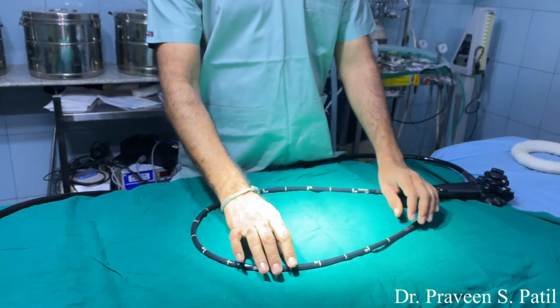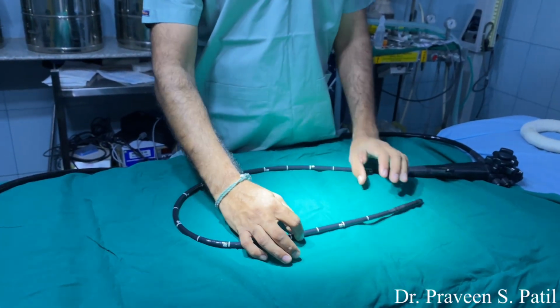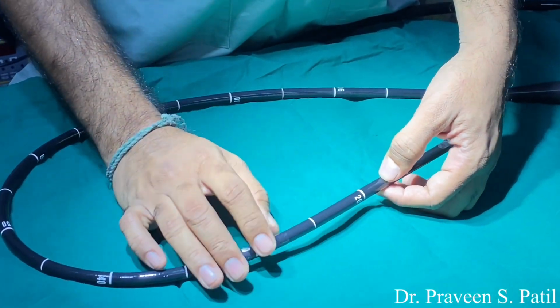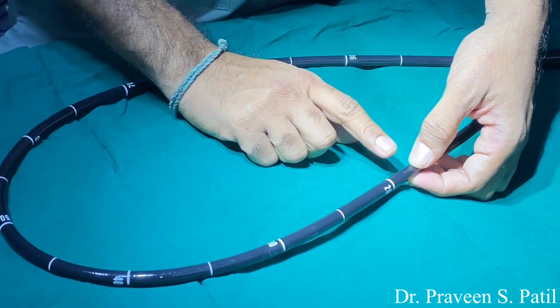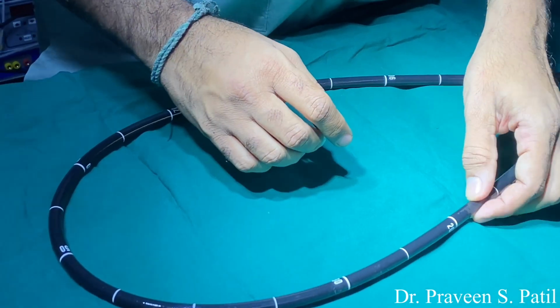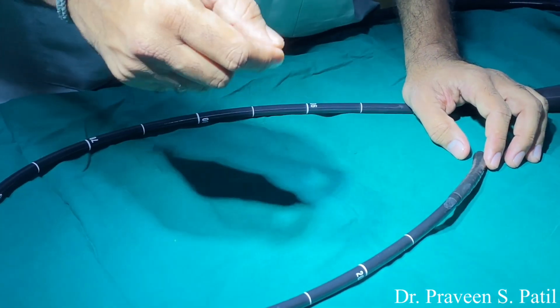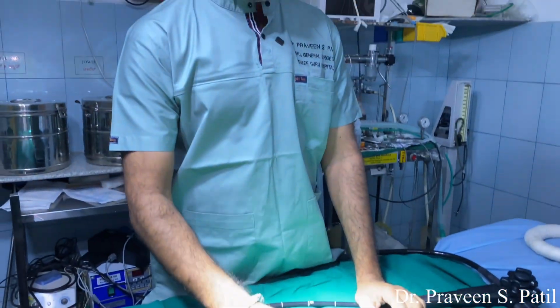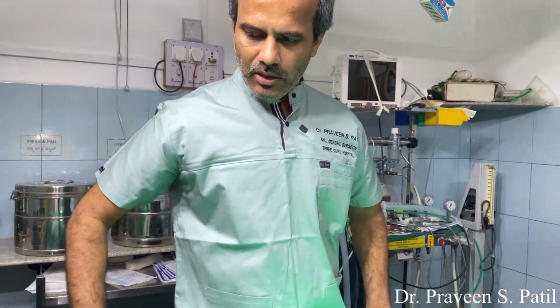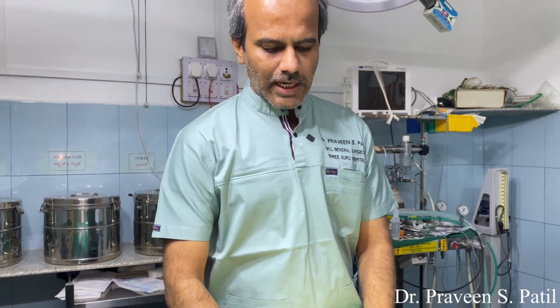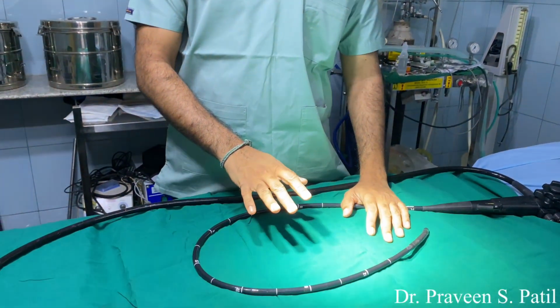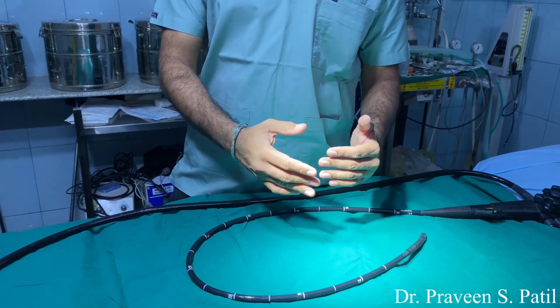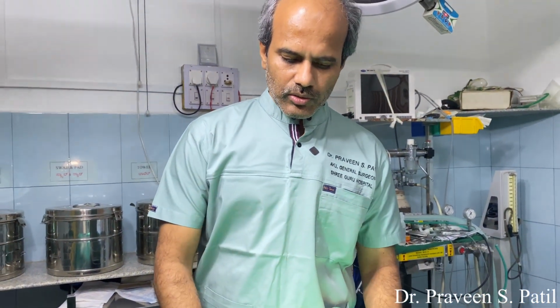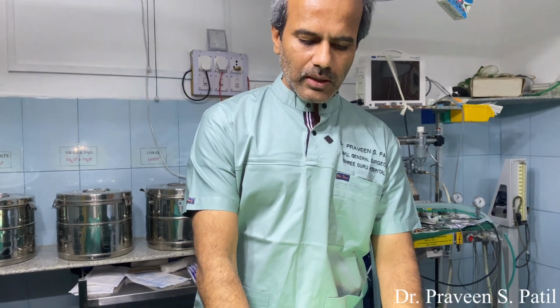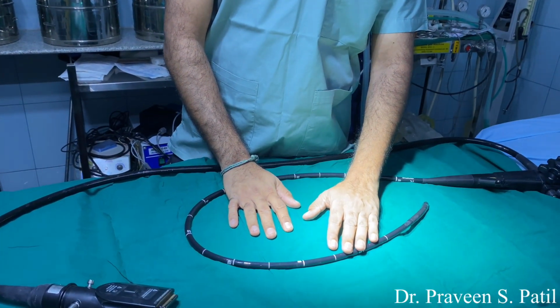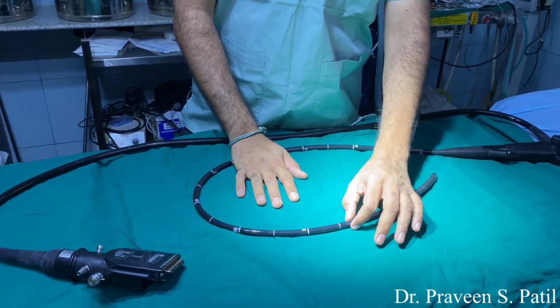And coming to thickness, the diameter of the insertion tube varies from 6 mm to 11 mm. If you are using the scope to insert through the nasal route, or in the pediatric age group, then we go for 6 mm, or else the normally used thickness is 9 mm. For procedures with the upper GI endoscope, you can go for comparatively higher diameter scopes. This one has a diameter of 0.9 centimeter, that is 9 mm.